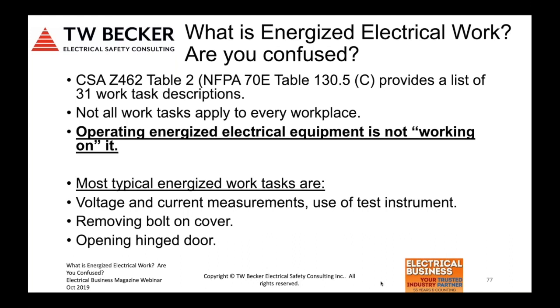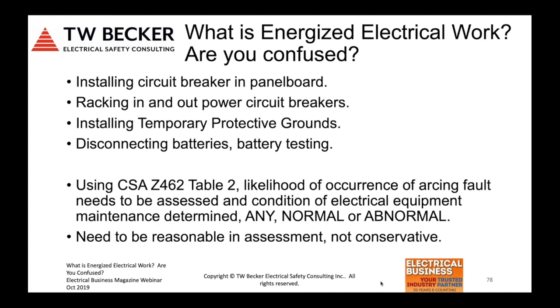So I also want to emphasize that operating energized electrical equipment isn't maintenance; when you're operating the equipment, you're not working on it. The most typical energized work tasks are voltage and current measurements, use of a test instrument, removing a bolt-on cover, opening a hinge door, if we define that as energized electrical work, which 70E and Z462 do, because behind the hinge door are energized conductors and circuit parts. I'm not discounting that, but not all electrical equipment has energized conductors and circuit parts behind it. And if it does, the voltage of them may not be high enough to create an arcing fault. Other tasks include installing a circuit breaker in a panelboard energized, racking in and out power circuit breakers, installing temporary protective grounds, disconnecting batteries, or battery testing. This is just an example of some of the work tasks listed in Table 130.5(C) in NFPA 70E or Table 2 in Z462.